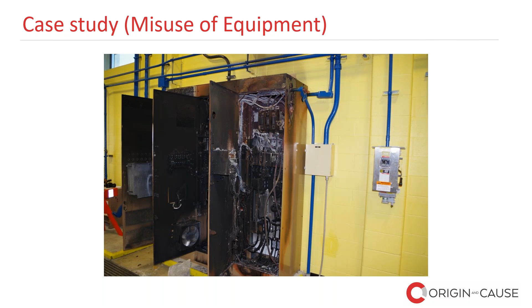This second case study involved a fire in a digester blower at a water treatment facility. When we had arrived for the investigation, equipment from the blower had already been removed and modified, which made the investigation much more difficult. And so as you can see again in the photo, what we actually had when we investigated this is there was a motor that was in this location and a rotary lobe blower, which is in this location, and then there's some cables connecting them, and that had all been removed and was actually out of the picture.